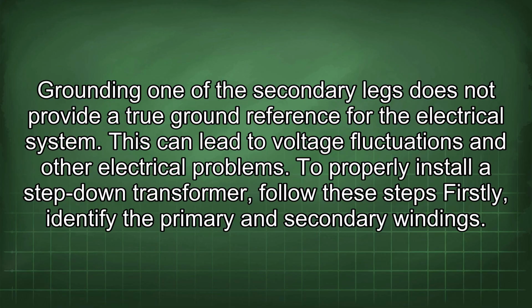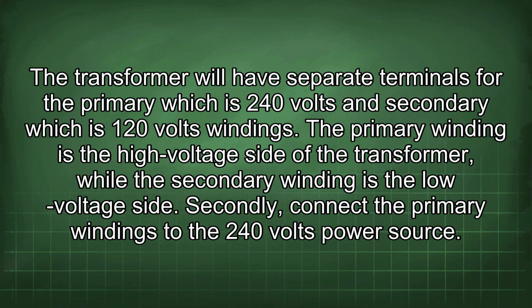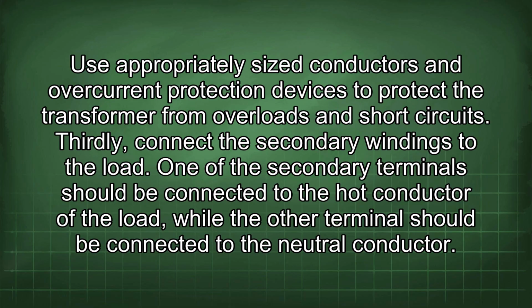To properly install a step-down transformer, follow these steps. Firstly, identify the primary and secondary windings. The transformer will have separate terminals for the primary, which is 240 volts, and secondary, which is 120 volts windings. The primary winding is the high voltage side of the transformer, while the secondary winding is the low voltage side. Secondly, connect the primary windings to the 240 volts power source. Use appropriately sized conductors and overcurrent protection devices to protect the transformer from overloads and short circuits.